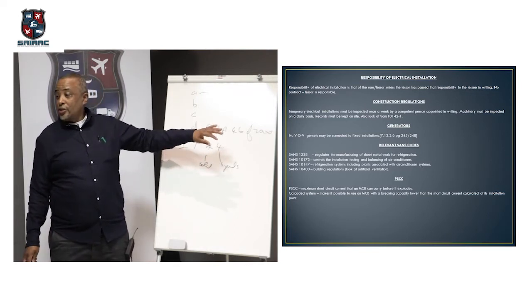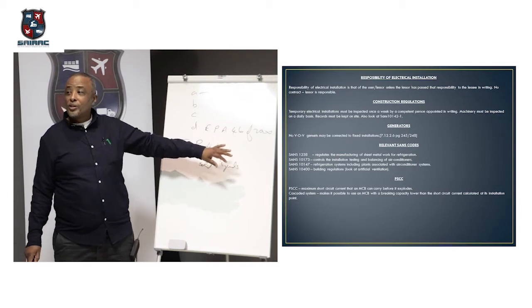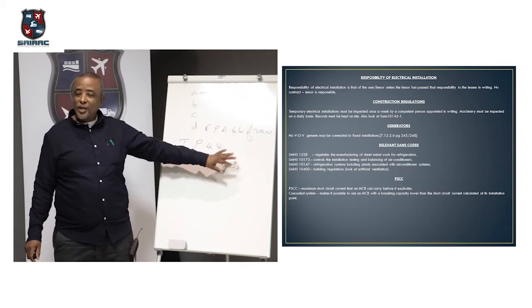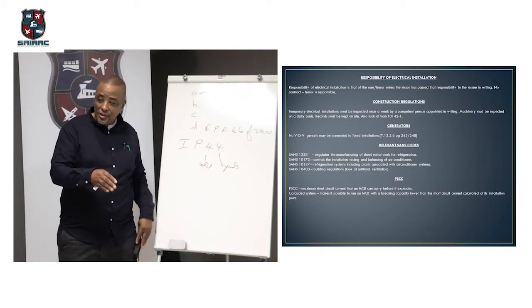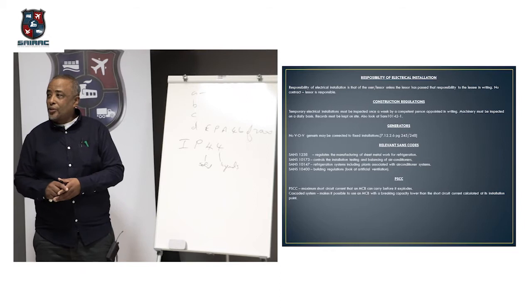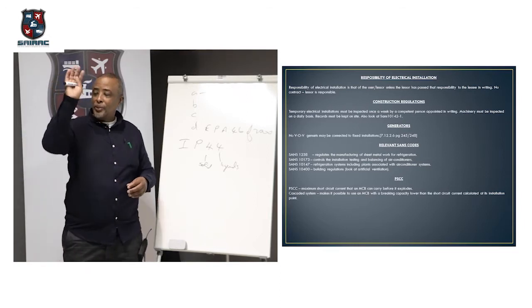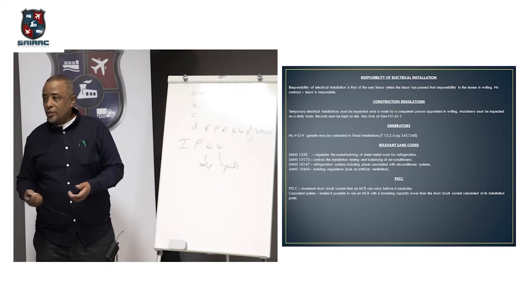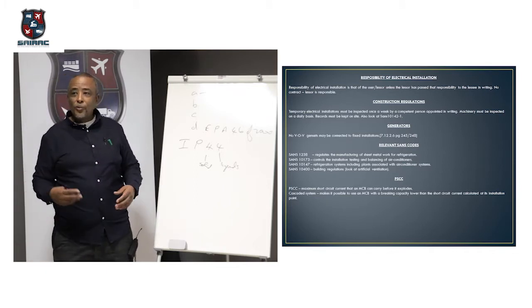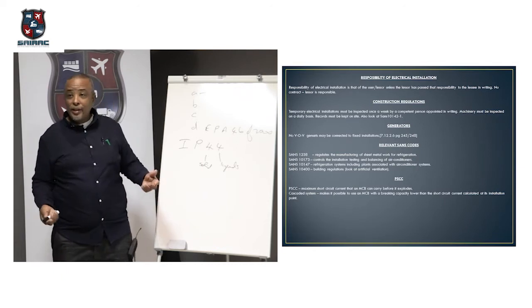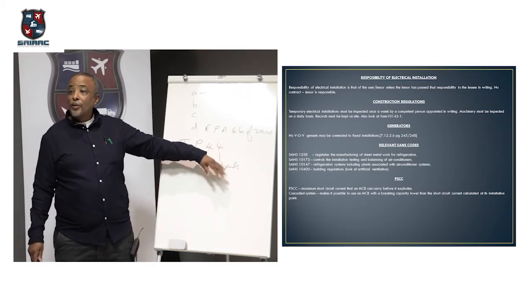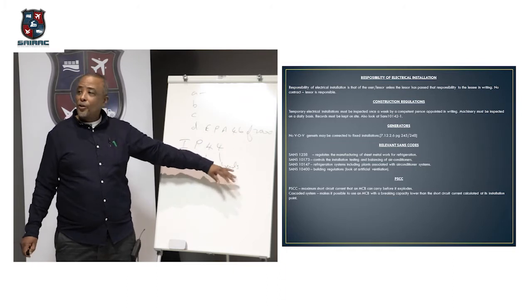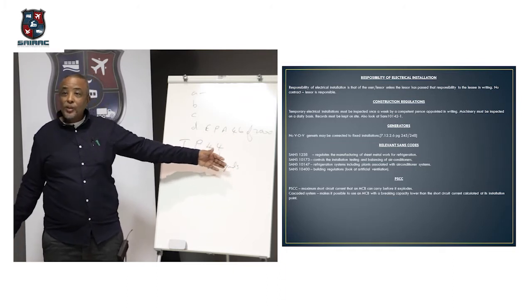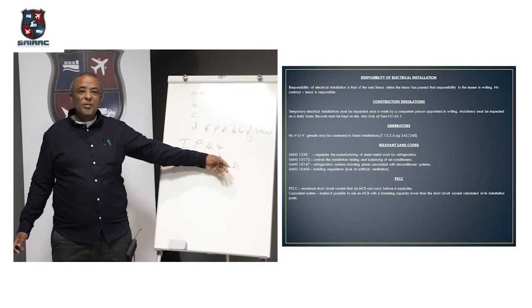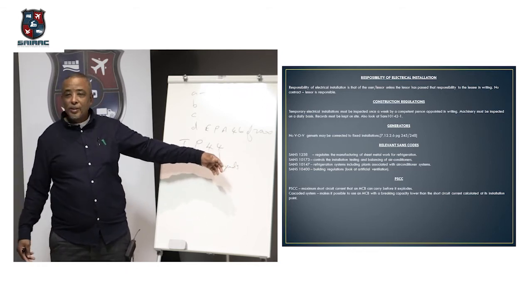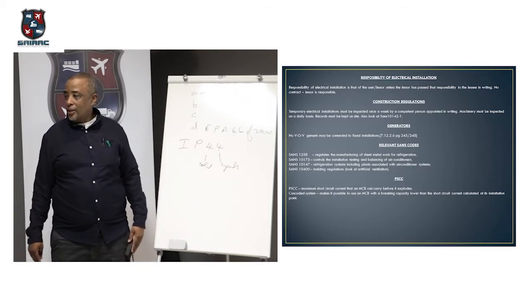Okay, unfortunately for the installation rules, guys, I always tell my students, don't worry about the table. The important thing is to know where the table is. And then when you go and buy a light fitting, you've got to know the environment. If it's a swimming pool DB that's outside, for instance, check it out. Is it going to be exposed to the full weather, most likely? Then you can choose maybe IP44. If you go to Voltex or wherever to buy something that's weatherproof, the guy is going to ask you, what is the IP rating? So, well, no, give me the best. This is, well, 3,000 Rand, whereas you could have got away with a 500 enclosure.